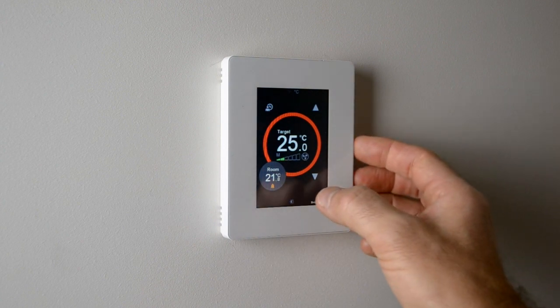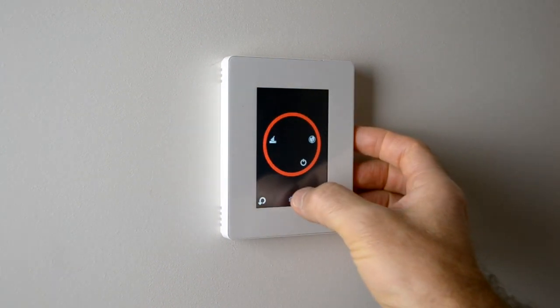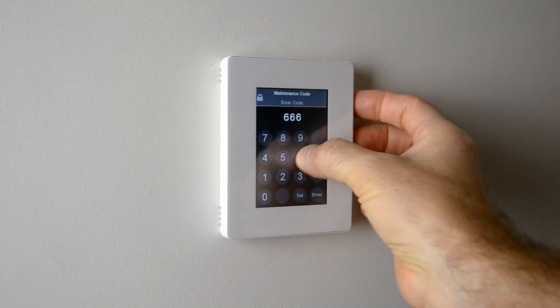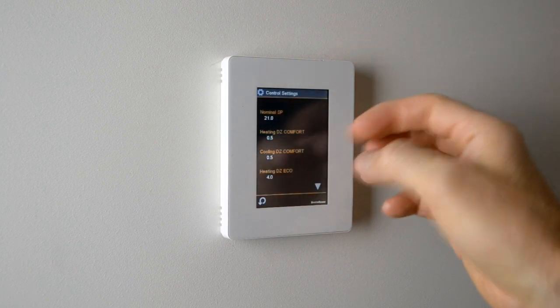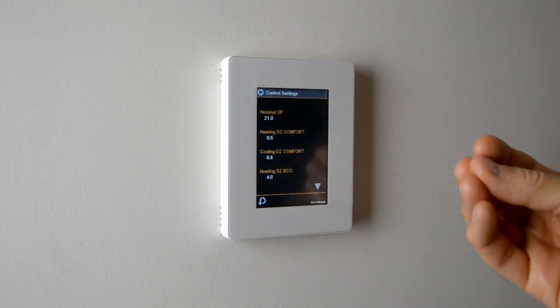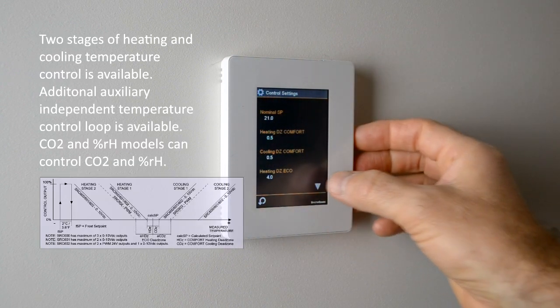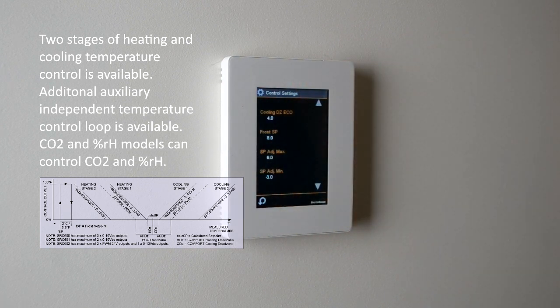In terms of the control settings, the controller is highly flexible. So if I again go to the settings, 6666, you can see if I go to the control operation, I can set the nominal set point. That's the set point where we normally control. I can set the dead zone settings on a comfort day mode. I can also set up different dead zone settings in eco mode. The cooling and heating dead zones can be asymmetrical, which allows, again, further energy savings. Typically, you would set up the heating dead zone maybe half a degree and the cooling dead zone possibly to 2 degrees, meaning that if the temperature set point is 21, the cooling only starts working after 23 degrees, saving significantly on that expensive cooling energy.